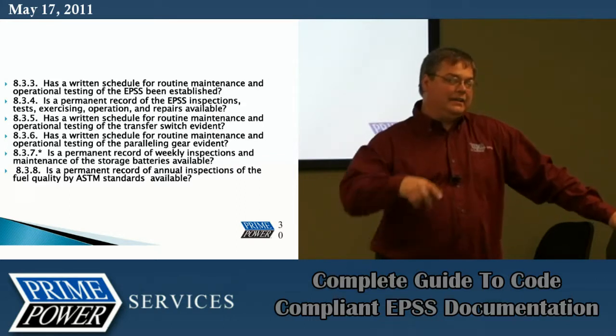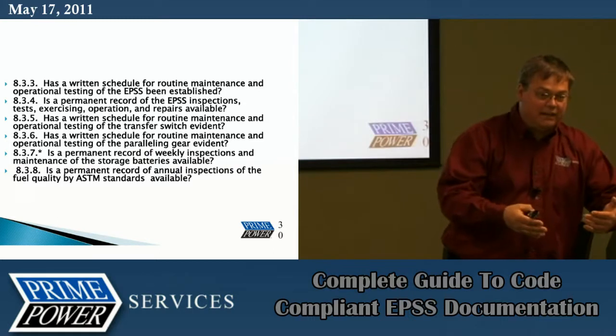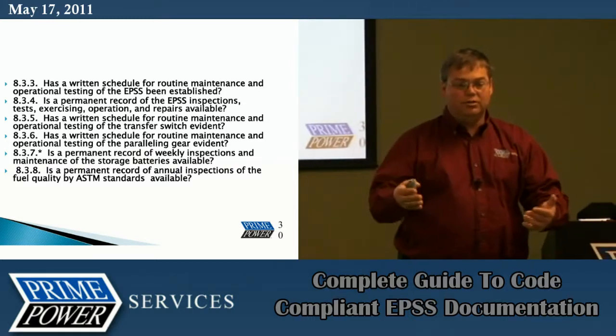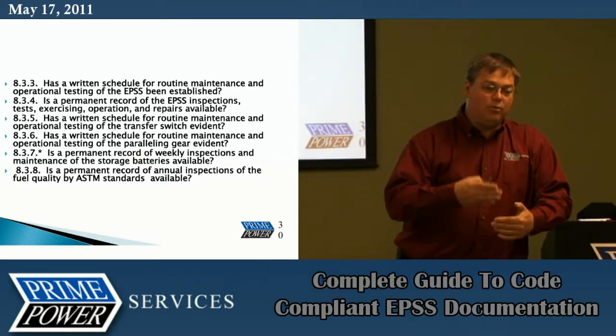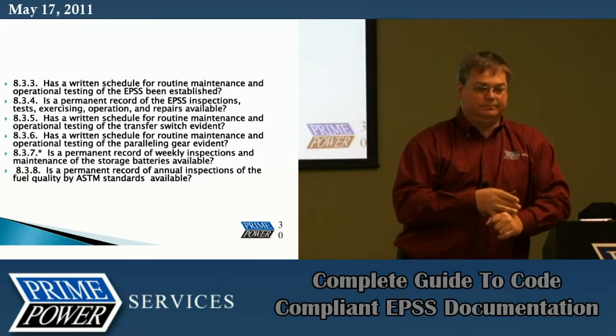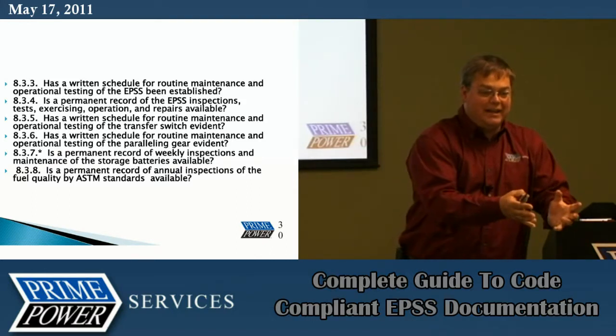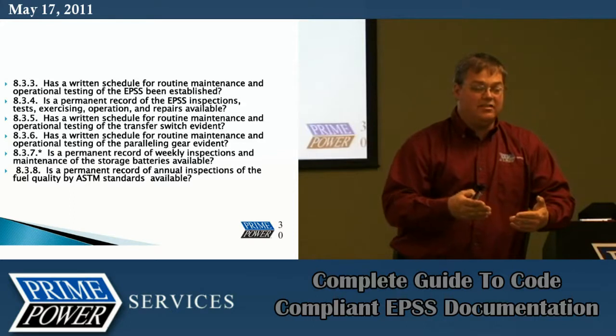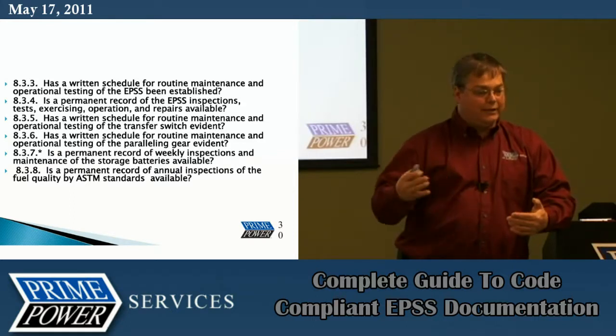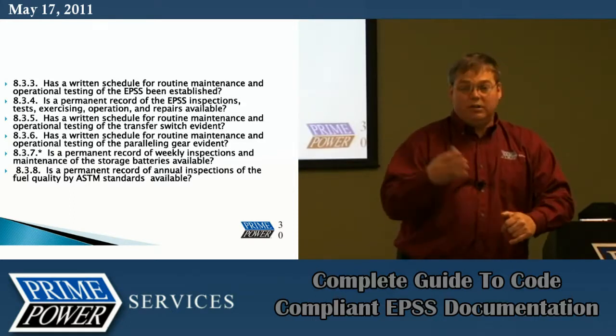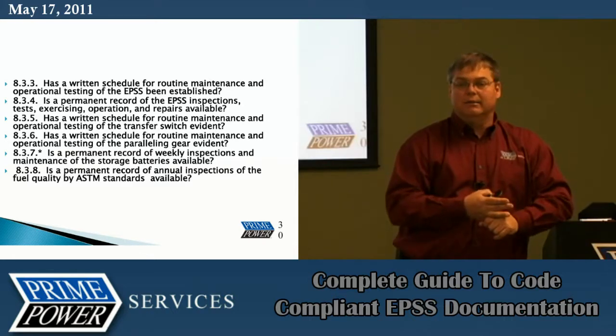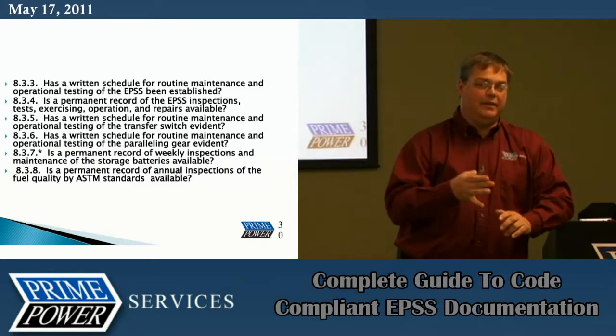I can't say for certain since I haven't discussed it with NFPA, but generally electronic copies are now acceptable, as long as you maintain a backup. You can't rely on just one PC to have it. It either needs to be web-based or backed up daily, weekly, whatever, on a disk. You need a backup for your electronic records, because what happens if that PC fails?